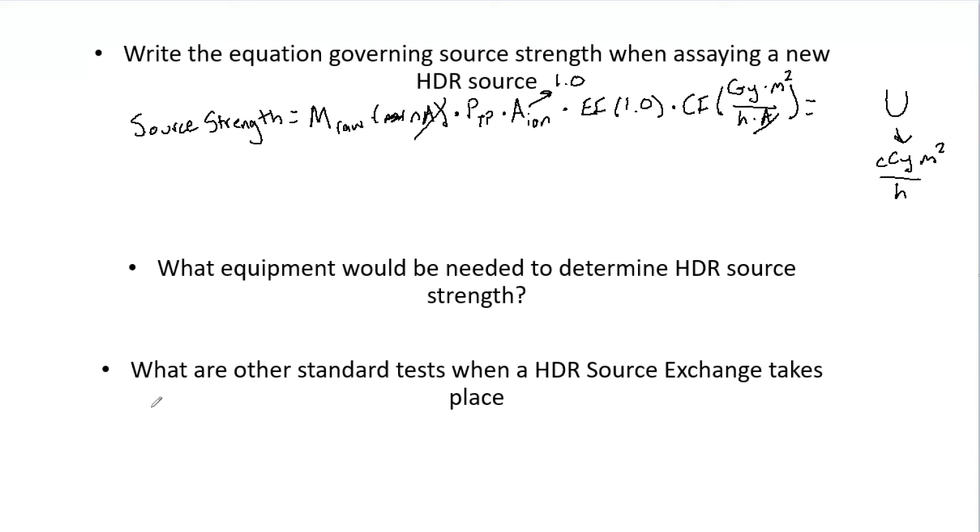And finally, what are some other standard tests you want to do? So this is simply what are you going to do for a source exchange. The first thing you want to do is a constancy check, so you want to do this before you even get your new source.